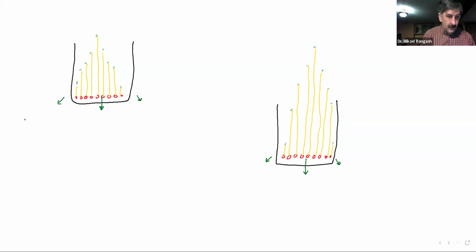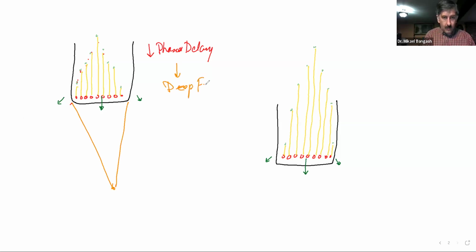And what we mainly said was that if the firing interval between this PZT to this to this to this to this, and likewise this to this to this to this, if we had a low, what we call, phase delay or a short phase delay, that was going to cause the beam to focus at a deep focal depth or point.